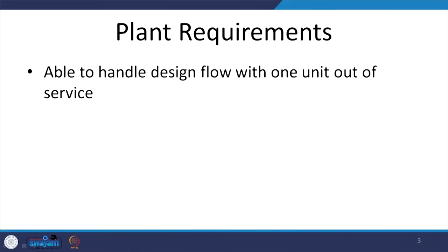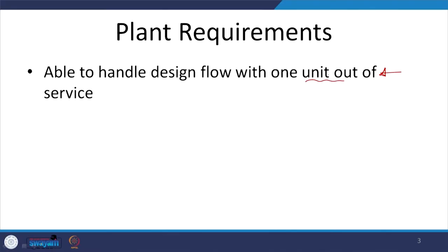So plant requirement in general, ideal case, depending on how well you design it and the capital costs, you want to design such that even when one of your unit processes, let's say sedimentation tank one, is out of service, there should be another standby sedimentation tank to be able to cater to the needs of the population. So that's what we have here: ability to handle design flow with one unit out of service.